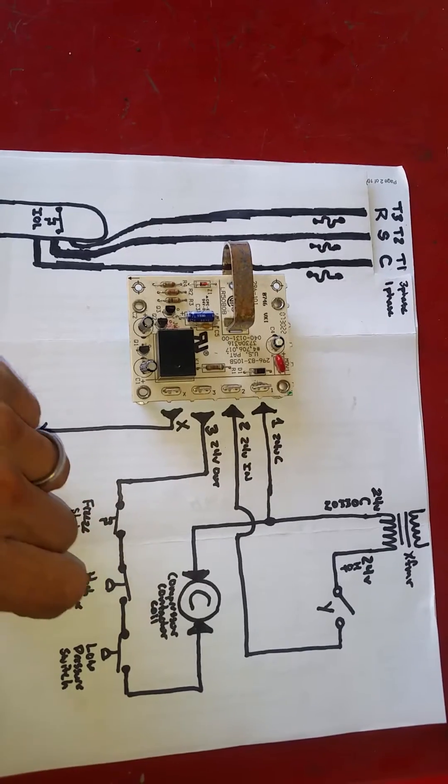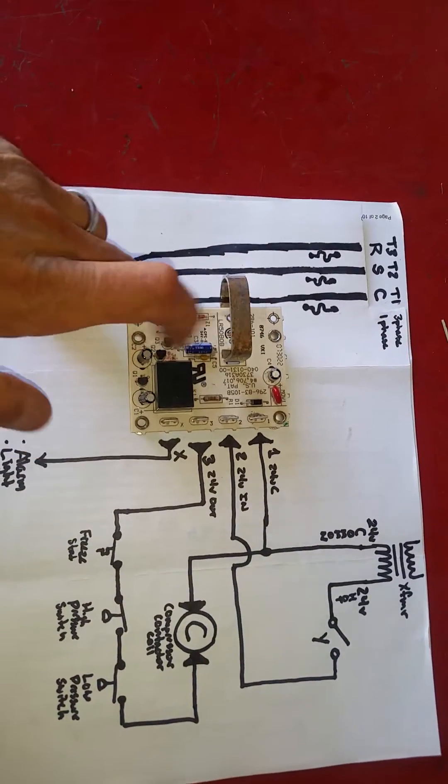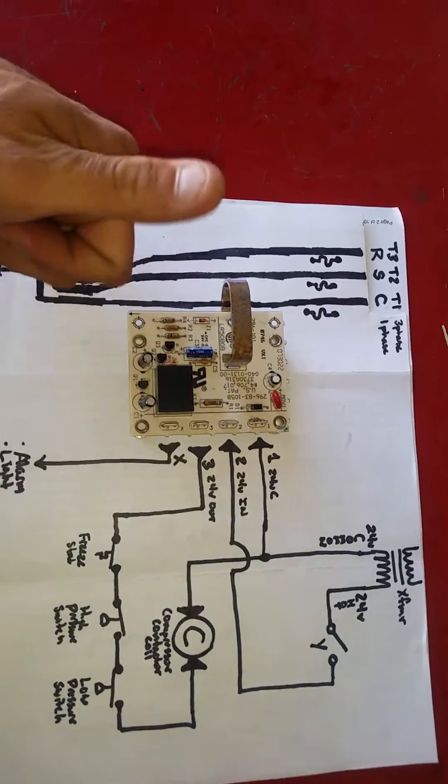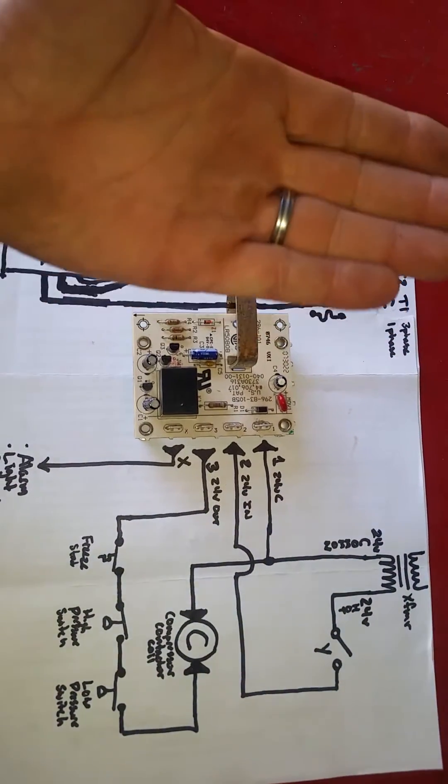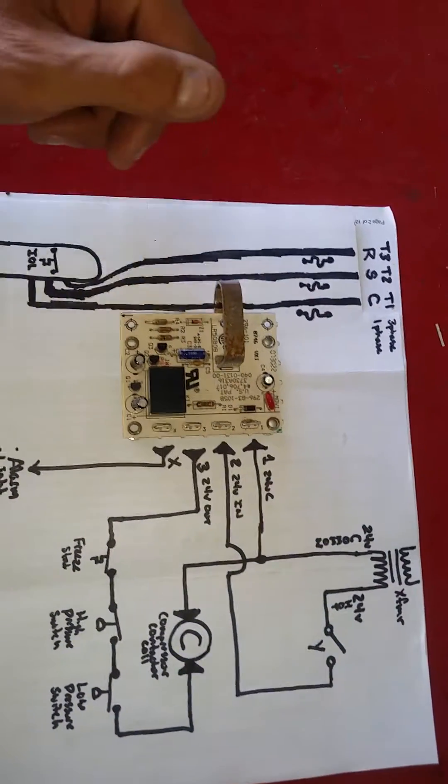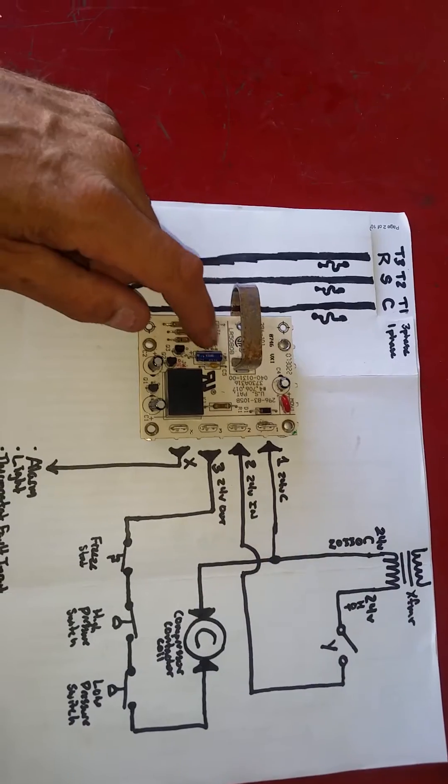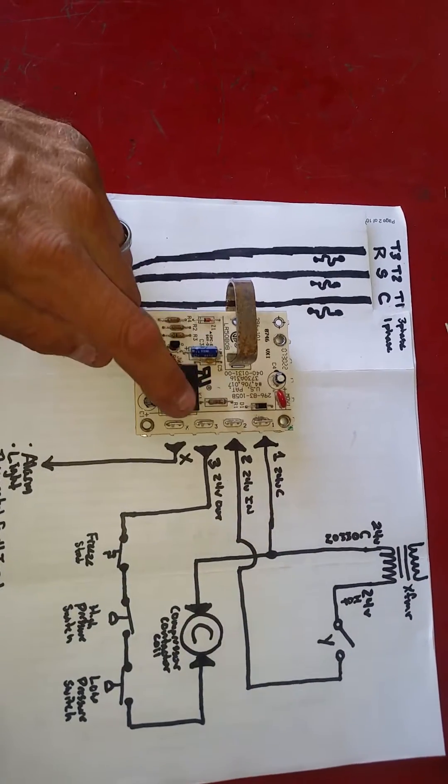Now, if the current sensor senses anything below 0.5, that means as the amperage drops below 0.5, after initial start up, 0.5 amps, the current will energize this circuit here and open this relay.